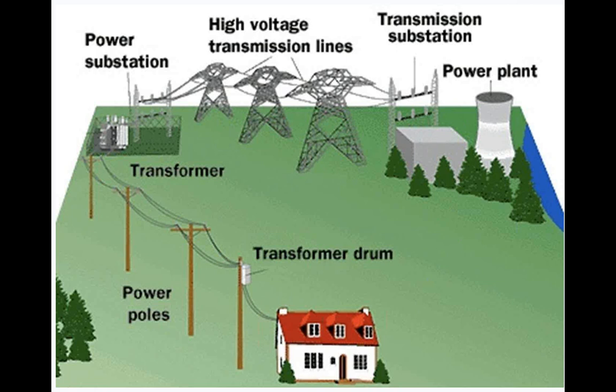Primary voltage or distribution voltage is always going to be the wires on top of the pole. That is going to be the highest voltage wires on any pole. From here to Hawaii, that's going to be the configuration. The highest voltage is going to be on top of that pole. It comes down in distribution voltage. Eventually you get to a customer. The customer typically doesn't want whatever that primary voltage is. In Connecticut, ours can be as high as 23,000 volts. The utilities can vary on that. But ours, 23,000 volts. Customer never wants 23,000 volts because the hot tub runs just a little too fast on that. So we step it down.